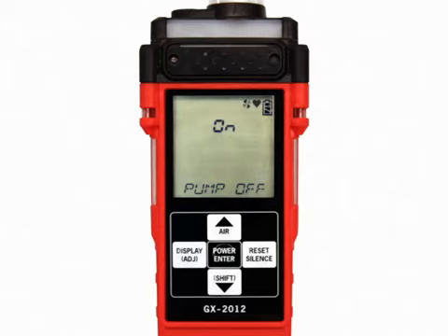In this screen, press Power Enter to turn the pump off. The fan in the upper right corner of the screen will disappear. Once the pump is off, you cannot exit this screen and return to normal operation or continue in display mode until you turn the pump back on. To turn the pump back on and continue in display mode or return to normal operation, press the Power Enter button again. Press and release the Display Adjust button again to proceed to the User ID screen.